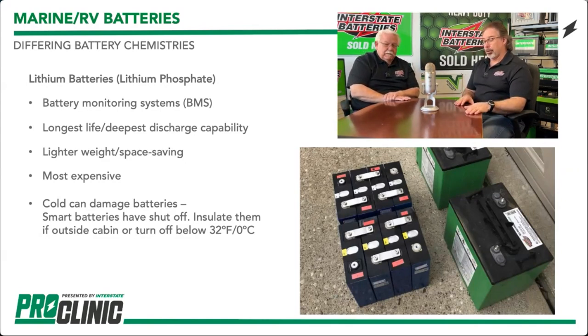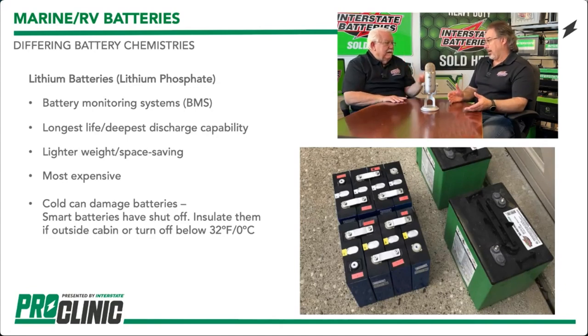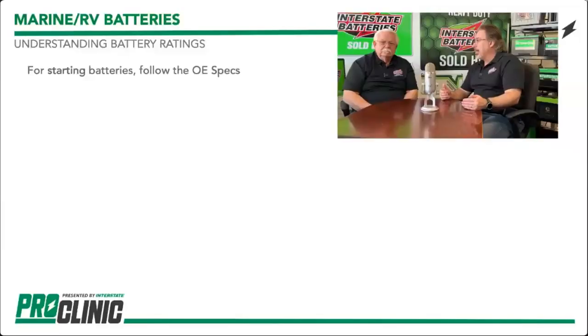The BMS keeps protection so the battery will not under-discharge or overcharge — there are parameters that prevent that. It's not only monitoring, it's helping to stabilize the battery — not overheat, and to function properly. Lithium is the most expensive battery out there. One drawback: lithium does not like cold weather. Some offer an internal heater to keep the battery warm, but keep in mind that internal heater is also drawing from the battery pack — anything that heats draws more power.